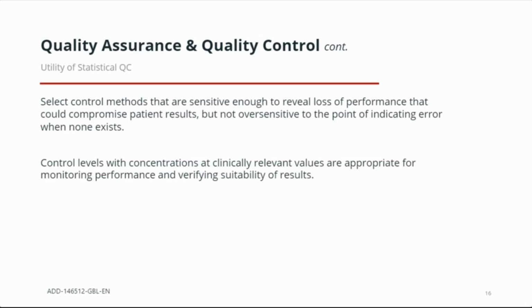Many factors weigh into our decision to purchase quality controls, whether that's purchasing from an ISO certified vendor, reliability of that QC material, performance, stability, cost, etc. The laboratory should select control methods that are sensitive enough to reveal loss of performance that could compromise patient results, but not overly sensitive to the point of indicating error where none exists. Also, control levels with concentrations at clinically relevant values are appropriate for monitoring performance and verifying suitability of results.